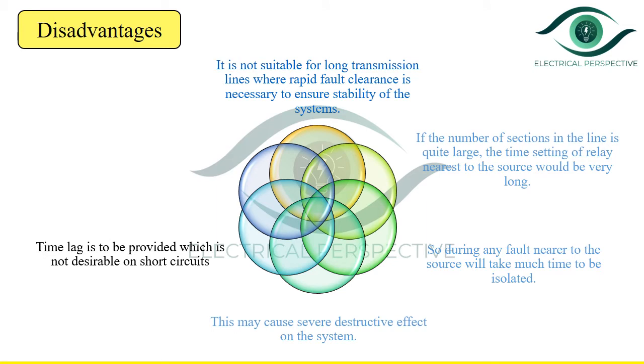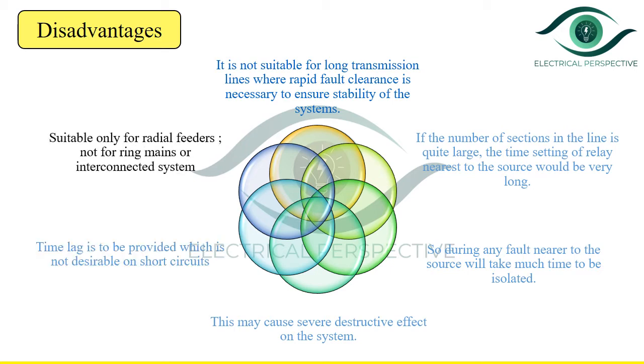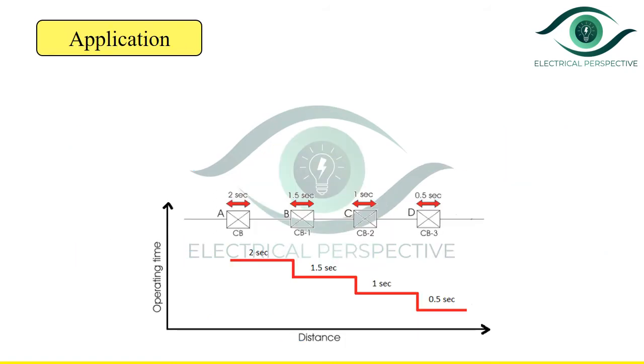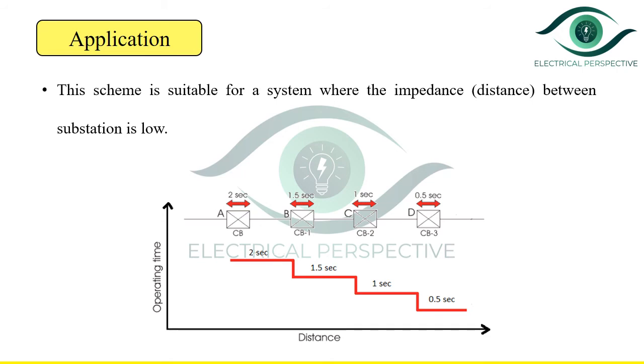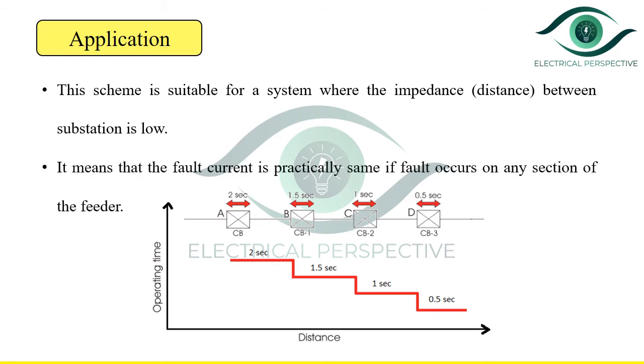Additionally, the time lag provided is not desirable for short circuits. This system is only suitable for radial feeders and is not suitable for ring mains or interconnected systems. Regarding application, this scheme is suitable for systems where the impedance — meaning the distance between substations — is low, so that the fault current is practically the same if the fault occurs on any section of the feeder.